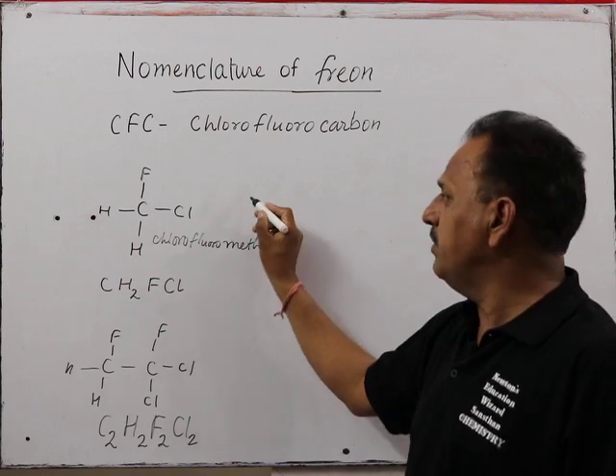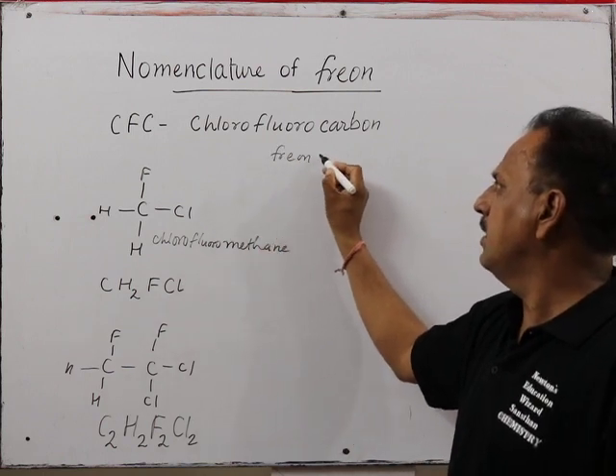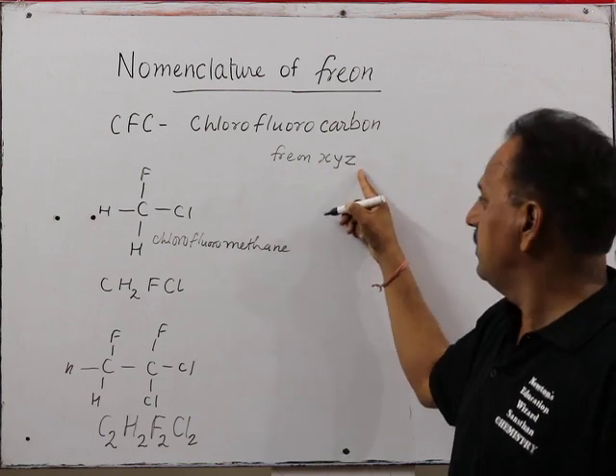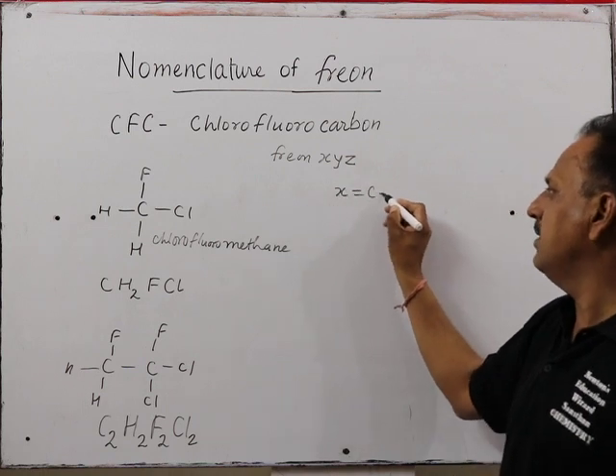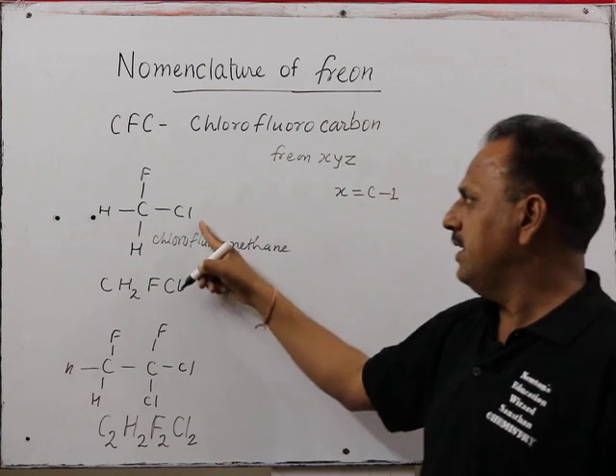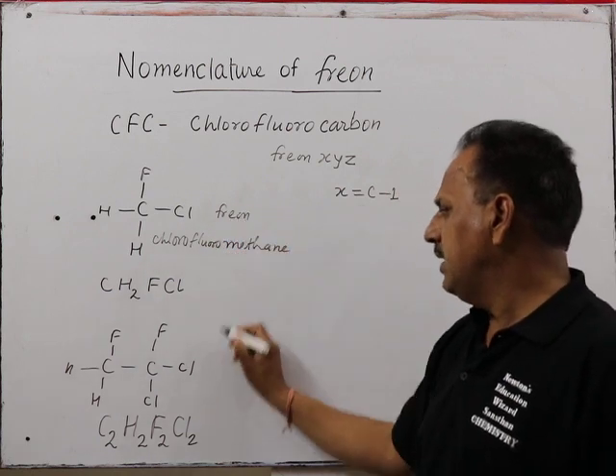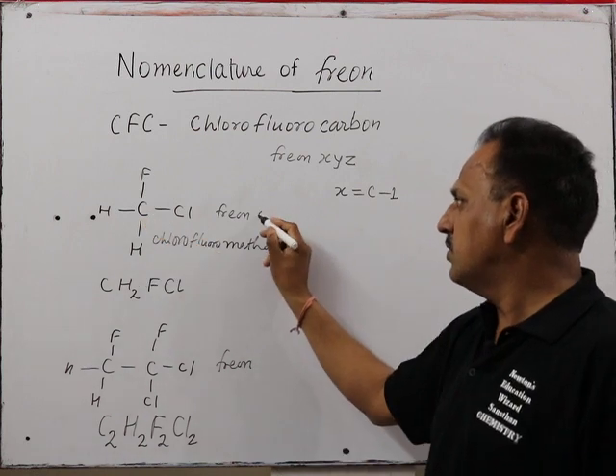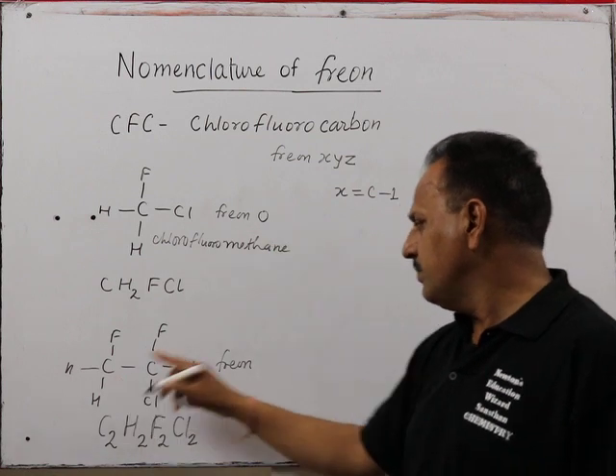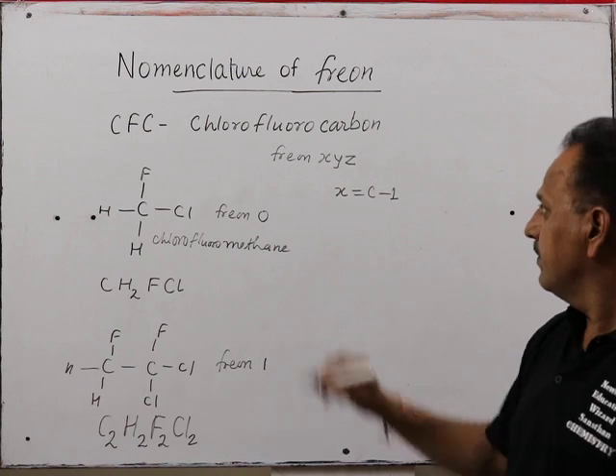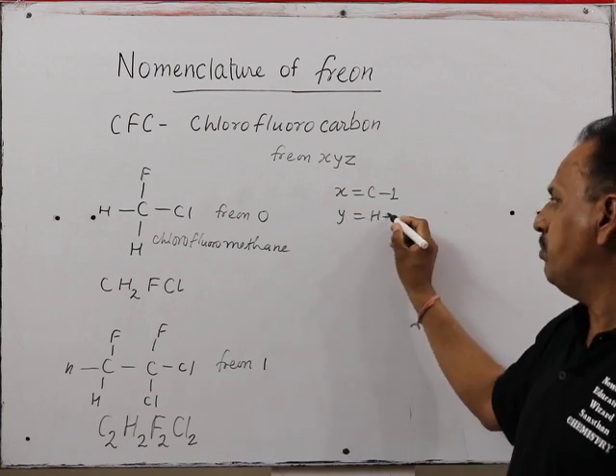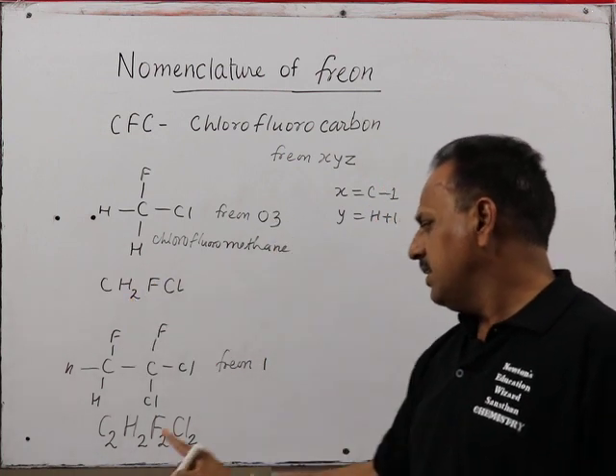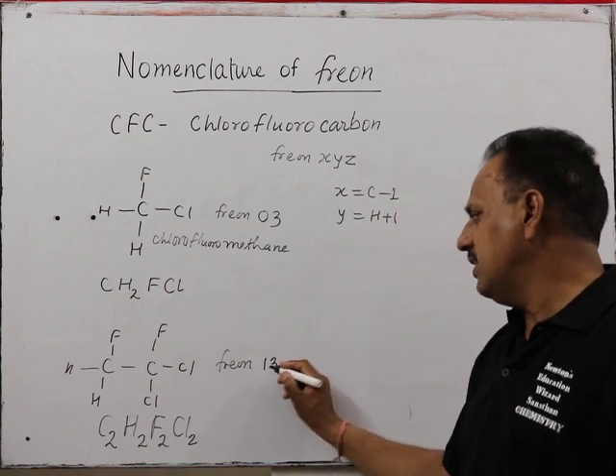In the Freon naming method, three numbers X, Y, and Z are used. X means the number of carbons minus 1. For one carbon, X is 0. For two carbons, X is 1. Y means the number of hydrogens plus 1. Here, 2 hydrogens plus 1 equals 3.